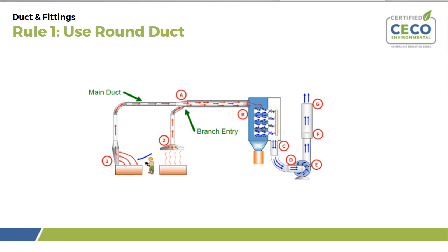Hello. We almost always use round duct in industrial ventilation systems. The only time you ever go to rectangular typically is if you're passing a duct through a confined space where the size of your round duct is not going to fit. Plus, round duct has the same strength over that circumference, whereas with rectangular duct, if it's wider than it is tall, you're going to have weaker spots, and calculating how thick it should be and what kind of stiffeners to use can become problematic.